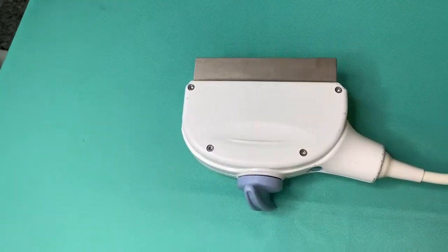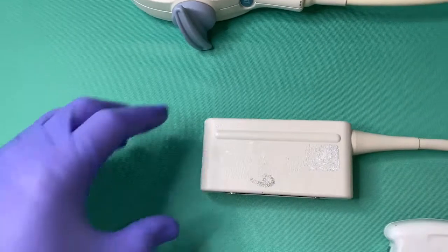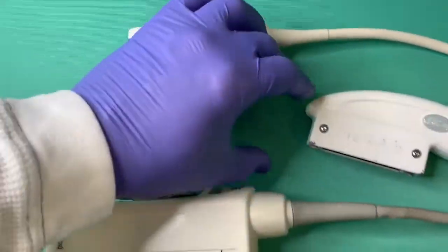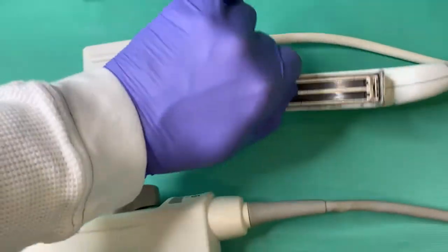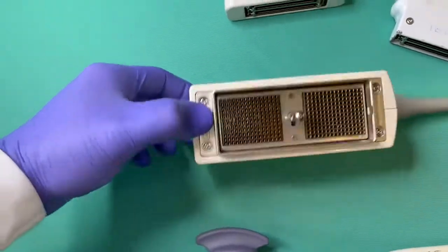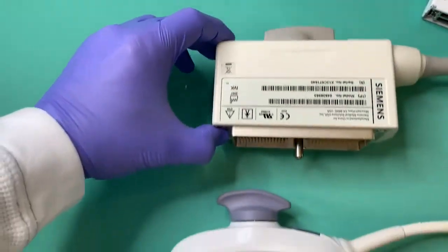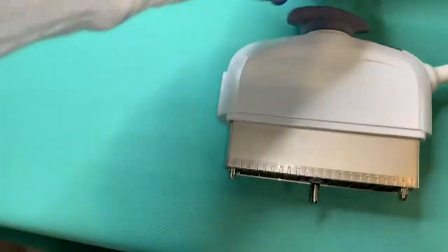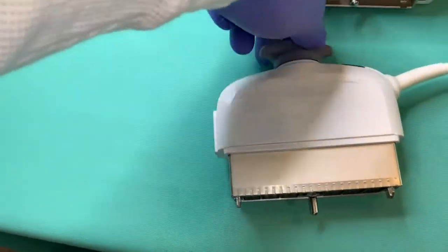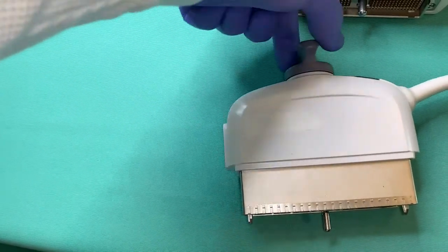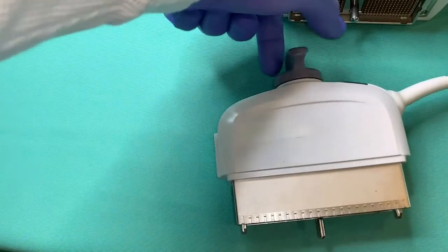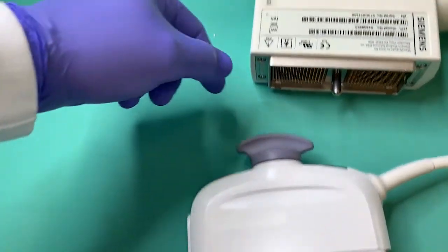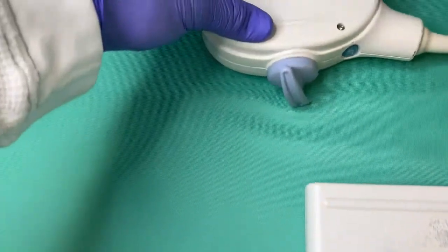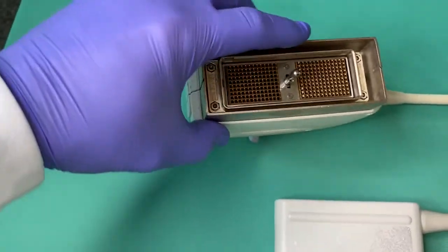There are multiple styles of system connectors. Some system connectors have a locking knob that is used to secure the connector to the scanner. The knob is attached to a shaft which extends through the connector body. The knob should be firmly attached to the shaft, and it should only rotate between 90 and 120 degrees, and it's model dependent. It should never rotate over 180 degrees or continually rotate.